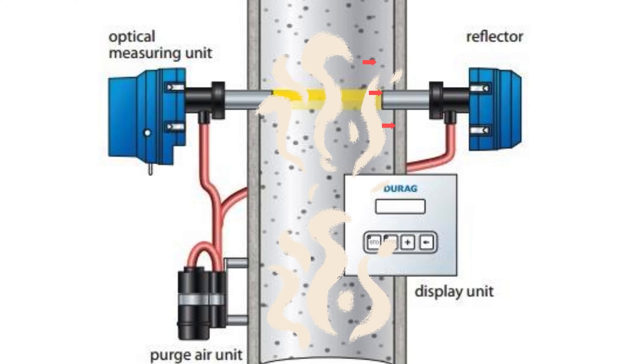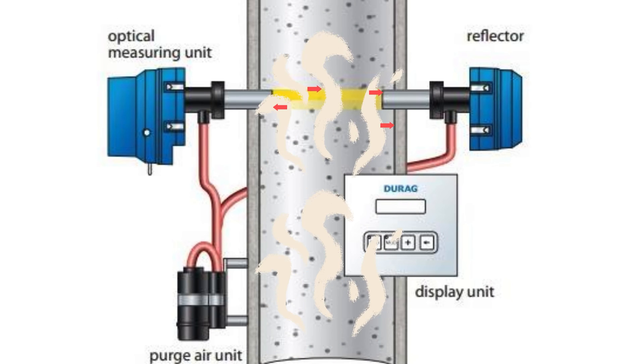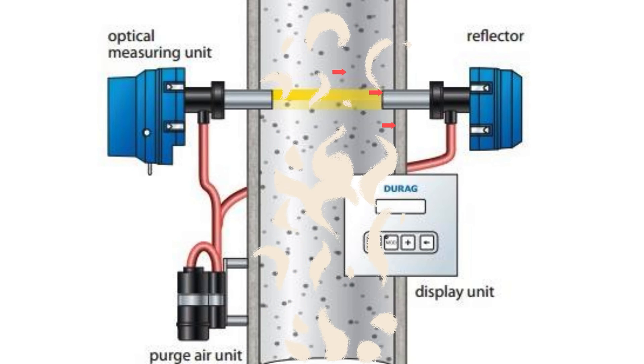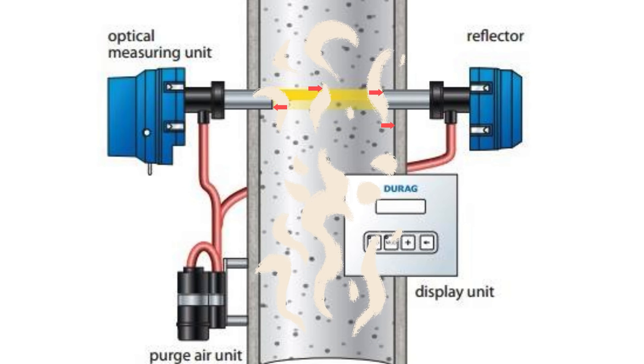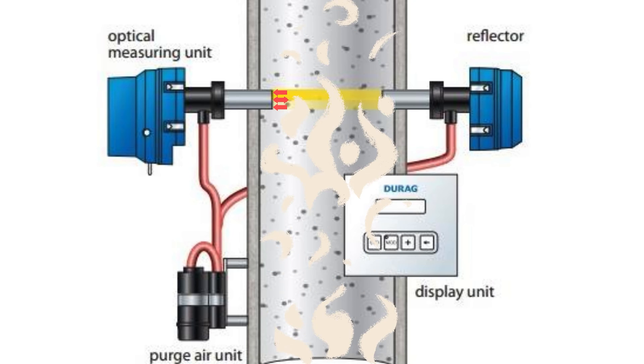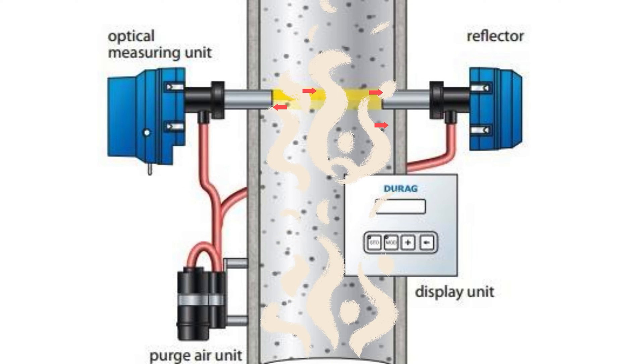Dust particles in the stack will absorb and scatter the transmitted beam of light, so the returned light will be less than the transmitted light. The ratio of the returned light to the transmitted light is called the transmission. One minus the transmission is referred to as opacity.